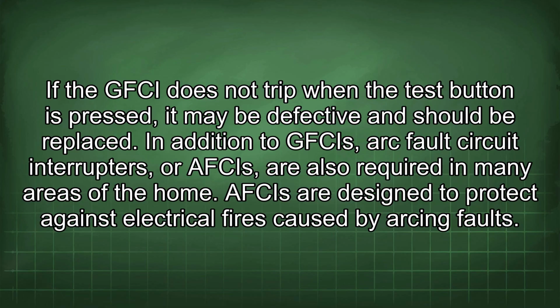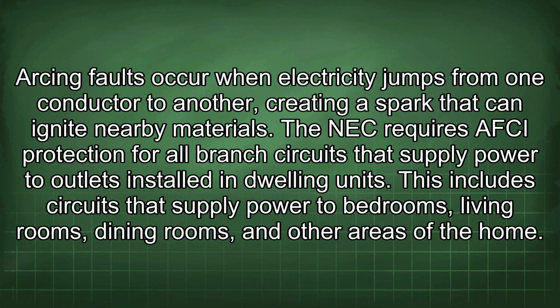In addition to GFCIs, arc fault circuit interrupters, or AFCIs, are also required in many areas of the home. AFCIs are designed to protect against electrical fires caused by arcing faults. Arcing faults occur when electricity jumps from one conductor to another, creating a spark that can ignite nearby materials. The NEC requires AFCI protection for all branch circuits that supply power to outlets installed in dwelling units. This includes circuits that supply power to bedrooms, living rooms, dining rooms, and other areas of the home.